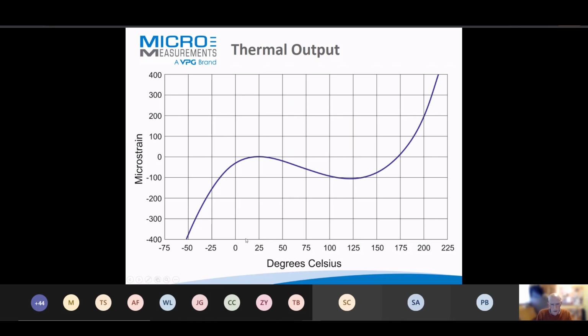The great thing is, around room temperature, this curve is virtually flat. So if you're doing laboratory tests, you'll have no measurable thermal output. If you do change temperature, say to 100 degrees Celsius, you might see around minus 90 microstrain. This curve is published with every pack of gauges, so you can plot it in an Excel spreadsheet or in your instrumentation for automatic correction.